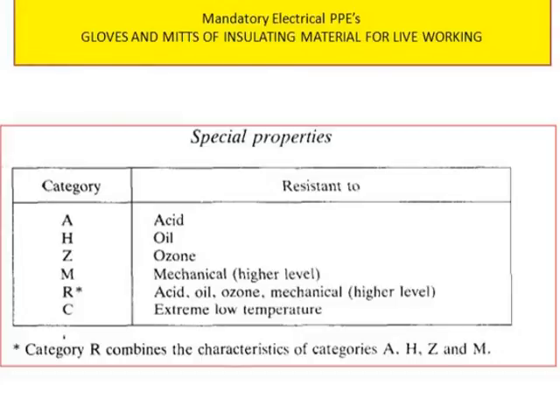There are special property categories: A, H, Z, M, R, and C. Category A must be resistant to acid. Category H must be resistant to oil. Category Z must be resistant to ozone. Category M must be resistant to mechanical damage. Category R combines the characteristics of A, Z, H, and M — resistant to acid, oil, ozone, and mechanical damage. Category C is for extreme low temperature.